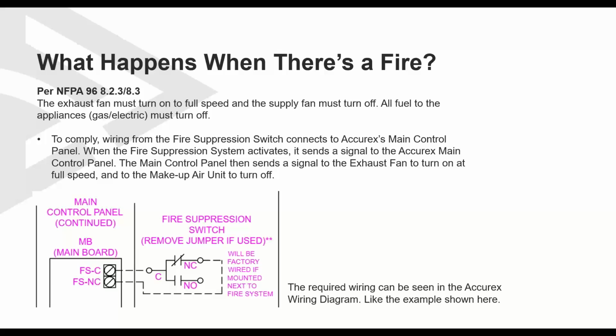Per NFPA 96, the exhaust fan must turn on to full speed and the supply fan must turn off. All fuel to the appliances, whether gas or electric, must turn off. To comply, wiring from the fire suppression switch connects to Accurex's main control panel. When the fire suppression system activates, it sends a signal to the Accurex main control panel. The main control panel then sends a signal to the exhaust fan to turn on at full speed and to the makeup air unit to turn off.